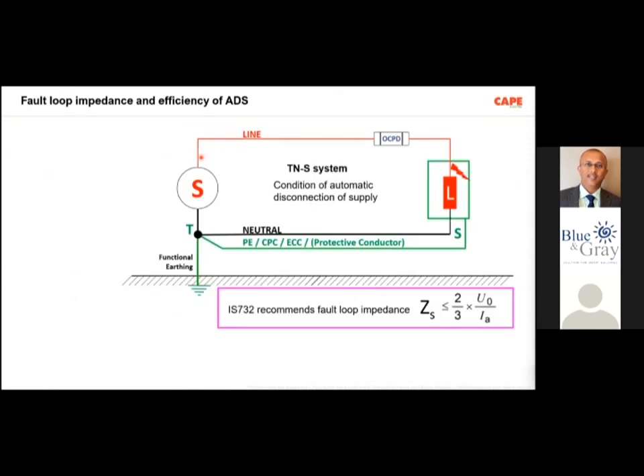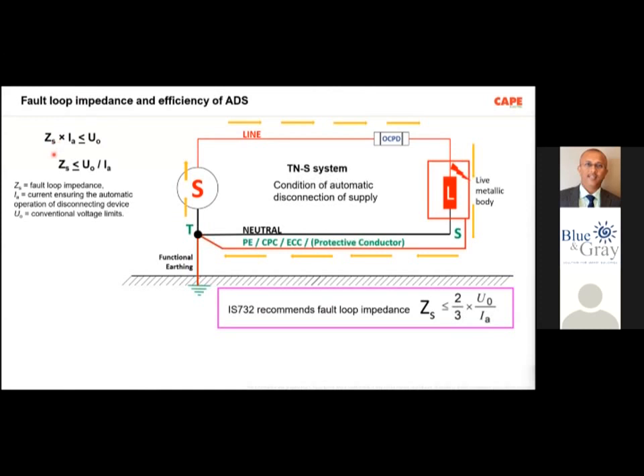So basically, what we are talking about is how to disconnect the supply. And disconnection of supply means you have to have a very low fault return path to the source. Fault current never goes to earth, it returns back to the source through a metallic conductor if you have one. That is the most efficient way. And now IS 732 says these calculations are given. The fault loop impedance shall be less than or equal to the operating voltage divided by the operating current of that particular OCPD. Now the rating of the fuse comes into picture, the rating of the MCB comes into picture, its disconnection current comes into picture, and then finally the fault loop impedance comes into picture.